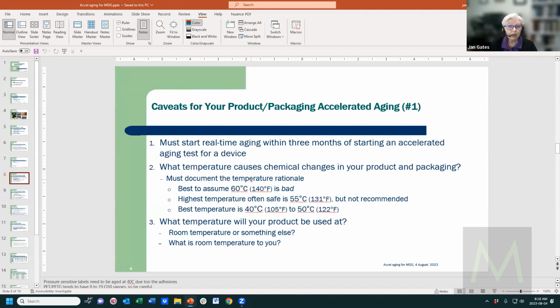Because I've had a problem with accelerated aging where we cooked the pouch just high enough that it released some agents into the package and caused the product to fail. But our real-time aging at the temperature level that we needed to do didn't show that and wasn't a problem. So you have to start them, and I look at that.